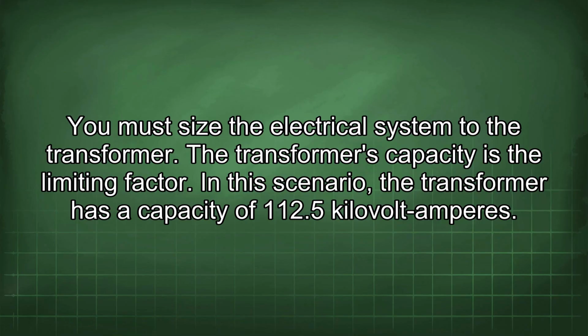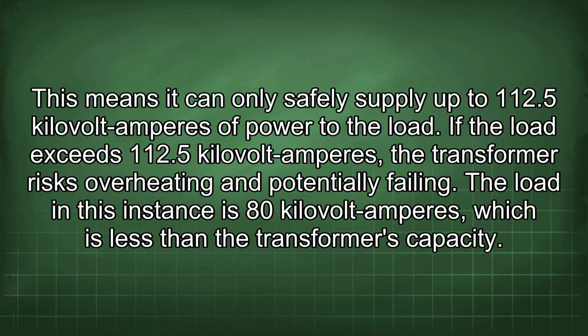You must size the electrical system to the transformer. The transformer's capacity is the limiting factor. In this scenario, the transformer has a capacity of 112.5 kVA. This means it can only safely supply up to 112.5 kVA of power to the load. If the load exceeds 112.5 kVA, the transformer risks overheating and potentially failing.